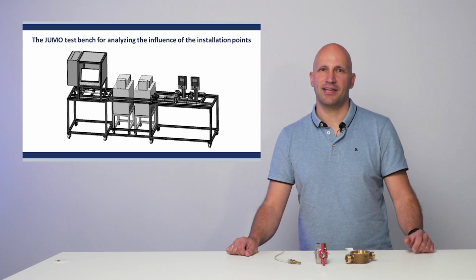In summary, it can be said that the installation of temperature probes, whether symmetrical or asymmetrical, has a major influence on the accuracy of the measurement. The heat conduction error in particular, which unfortunately you cannot see with your eyes, has a major influence on the calculation. However, with these basic principles mentioned here, you can ensure in practice that the measured values really do correspond to the actual energy consumption.